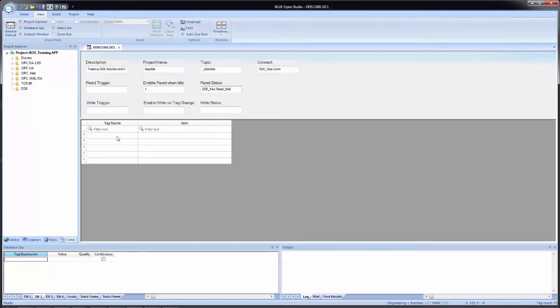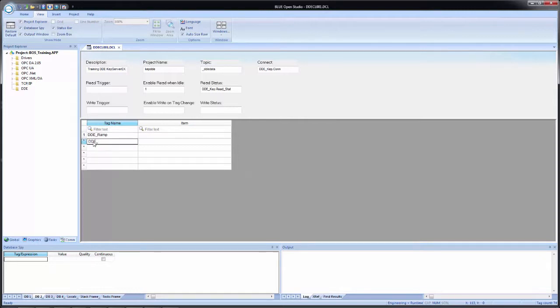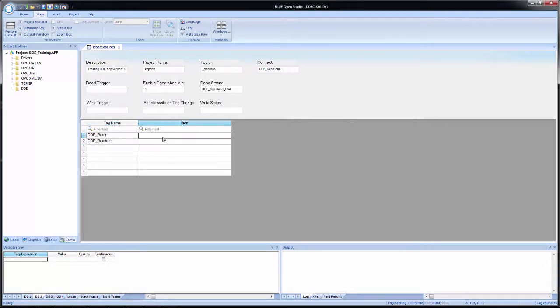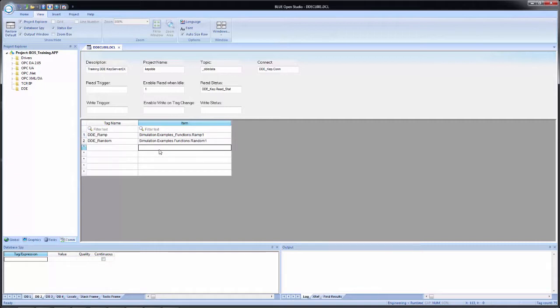Now in the body of the worksheet I have to enter in the tag names. I'll create two new tags: the first will be DDE underscore ramp, leave it as an integer, set the scope to local. The second will be DDE underscore random, leave the type at integer, set the scope to local. For the items, there is no browse because this will not connect to a server like OPC will. I have to go into my DDE server and find the actual item name. I've already done that and have them on a notepad, so I'll paste them in. The syntax is the same as what we used to set up OPC UA.